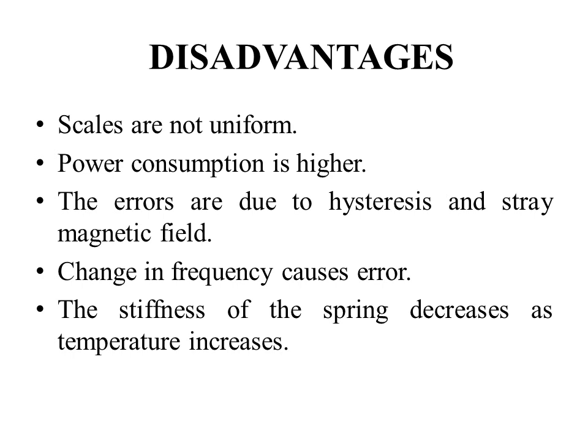The disadvantages of moving iron instruments are: compared to PMMC, the scales are not uniform; power consumption is very much higher for low voltage ranges; errors are caused due to hysteresis in the iron and due to stray magnetic fields; in AC measurements, changes in frequency cause serious errors; and with an increase in temperature, the stiffness of the spring also decreases.